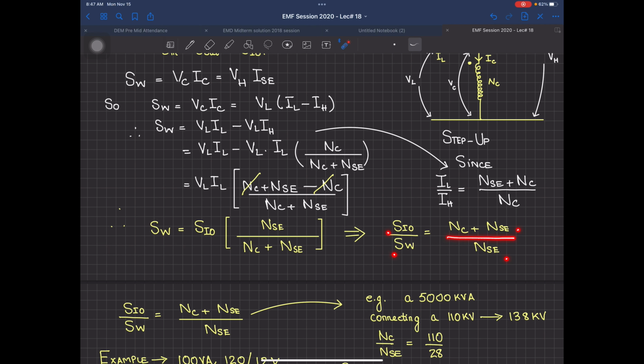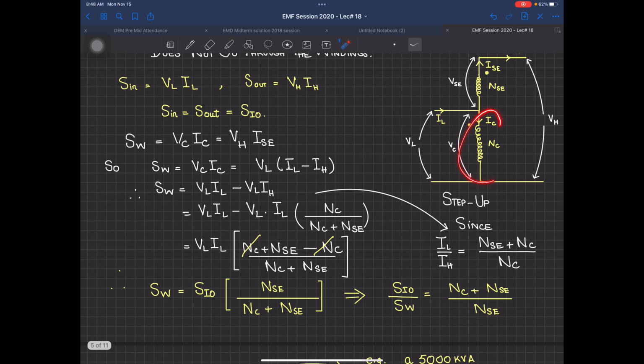What does this ratio tell us? SIO is the total power the transformer is handling, and SW is the power of the winding. So total power divided by winding power gives the advantage, as an empirical formula: SIO divided by SW equals NC plus NSE divided by NSE. So the larger the value of NC compared to NSE, the greater the advantage.